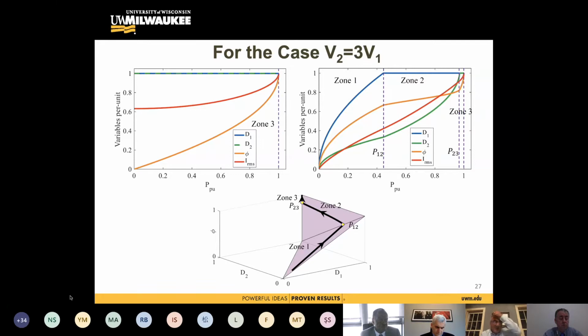When you change phi, you change the power, which is the horizontal axis here, and with that you get some RMS current, which is the red curve. If you do the traditional method, even at 0 power transfer, you have somewhere about 0.63 or so per unit of RMS current. This current isn't doing anything but transferring reactive power from one side to another, it doesn't do any good, it's just creating loss.